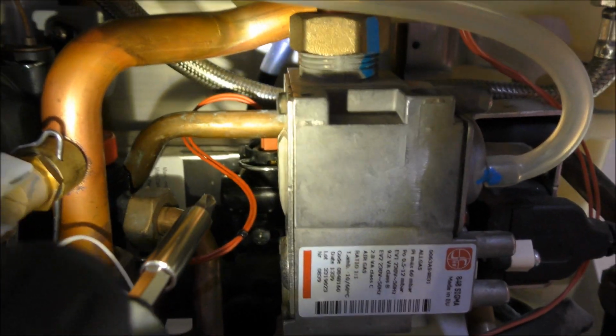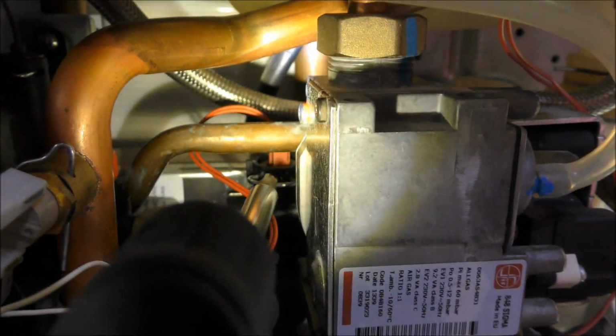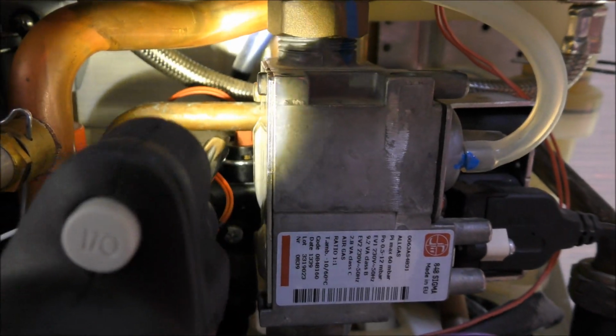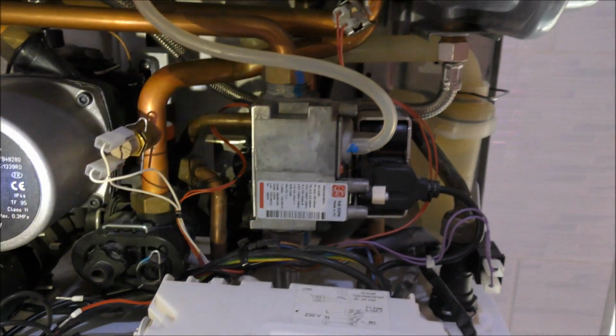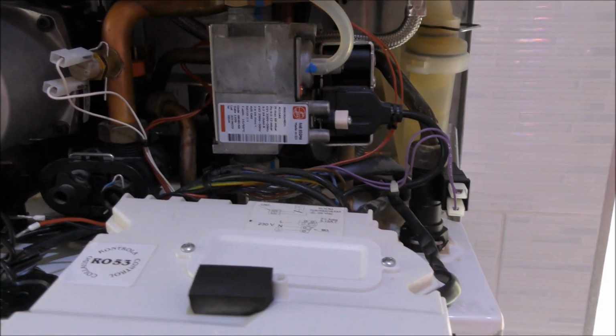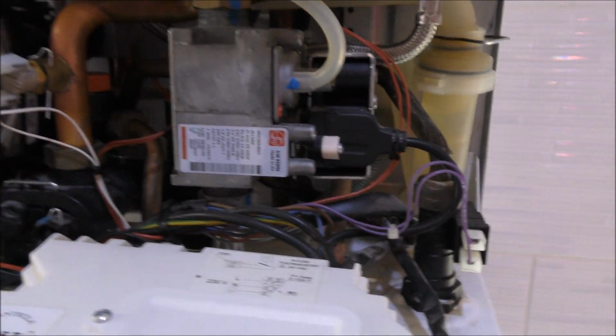There we go, okay, so that needs 4 bolts to go back. Then I'll be working on this rascal over here - that's where the thermistor is. I've got to pull that cable out, get this out, replace it, test it, and see if the problem has gone away in terms of the temperature drop.